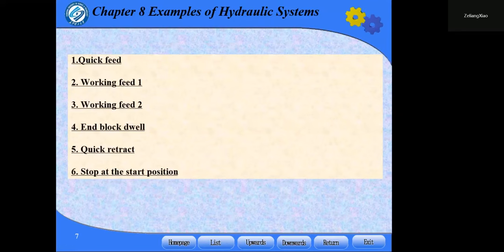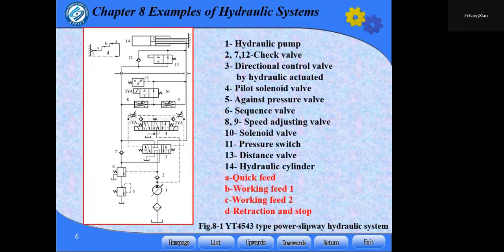When the button is started, the solenoid is energized and the pilot valve shifts the lever position. When it is in its left position, all the hydraulic oil direction will go straight towards the right, which makes the left piston of valve 3 into the system main oil line. The main oil line is from pump 1.